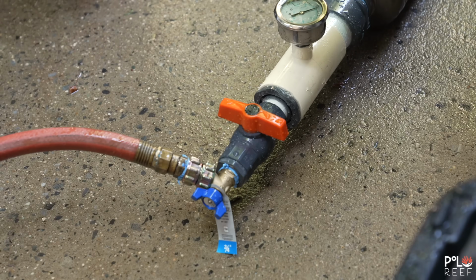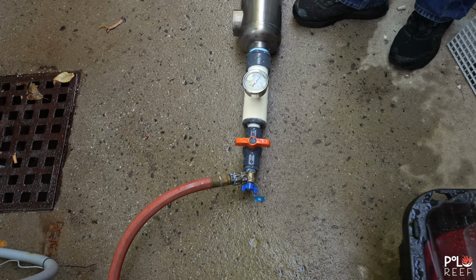Joe and John get to work pressurizing the exchanger and letting it sit. We charged it to 110 PSI with water. We purged out all the air, and now we set a timer for 30 minutes. We'll see if it drops when the timer goes off. For now, the team will have to be patient.